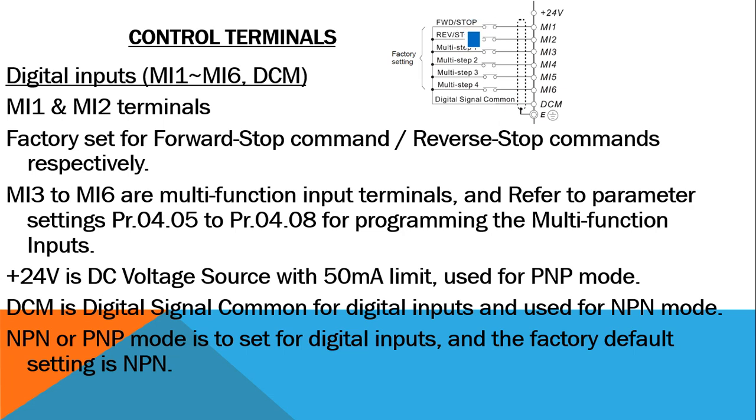So these two terminals are reserved in the VFD of Delta EL series for forward stop and reverse stop commands, and these are programmable digital inputs. What is programmable? MI3 to MI6, that is 3, 4, 5 and 6, so 4 terminals are there. It is programmable, not fixed for a single option only. Multiple options are there. That is why it is known as multi-function input. A wide variety of functions can be done by these input terminals.